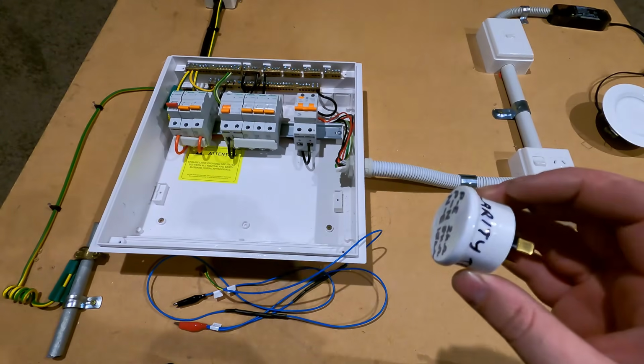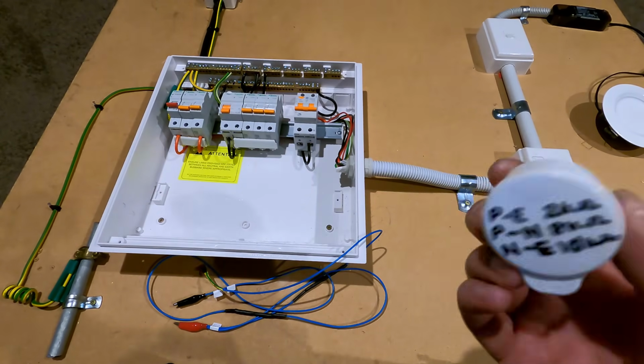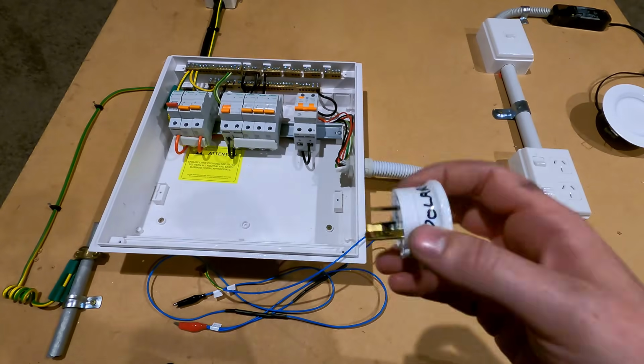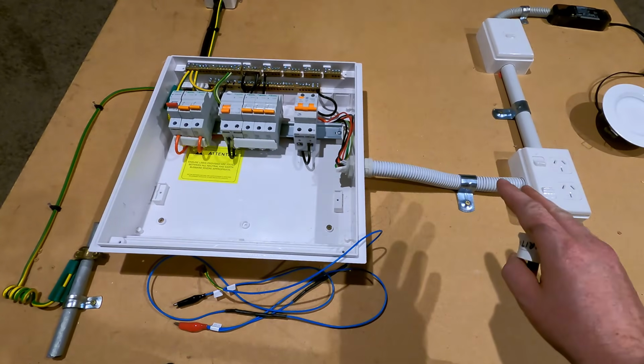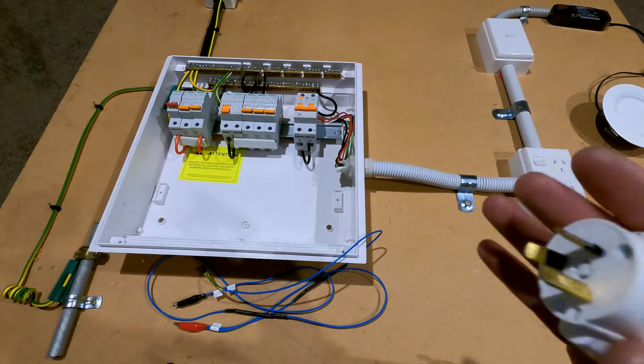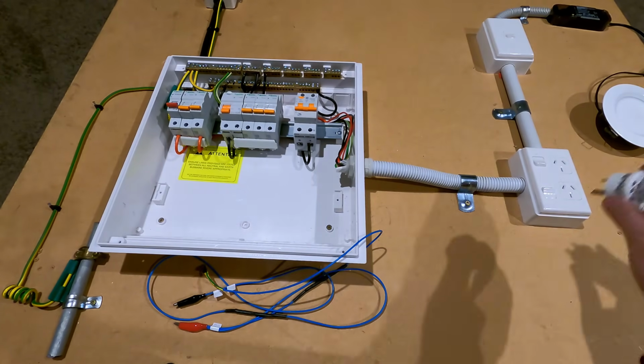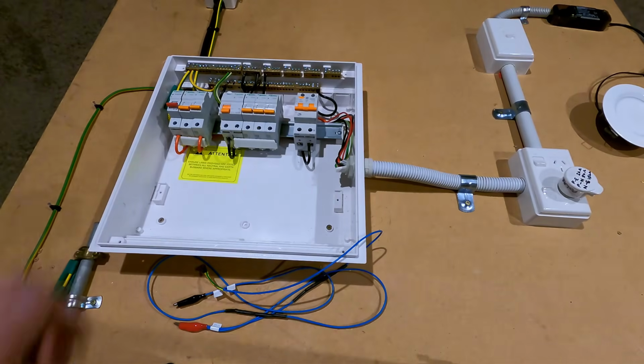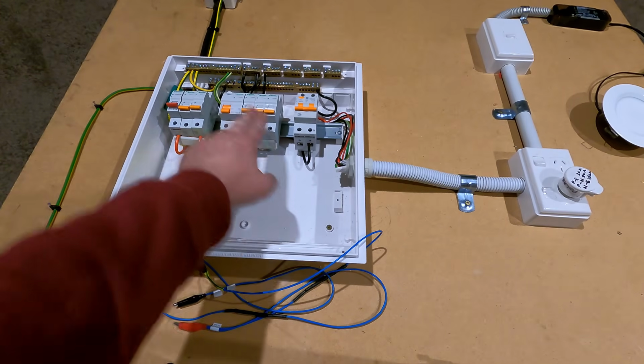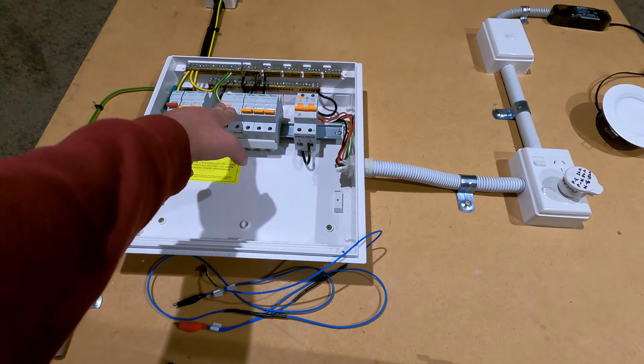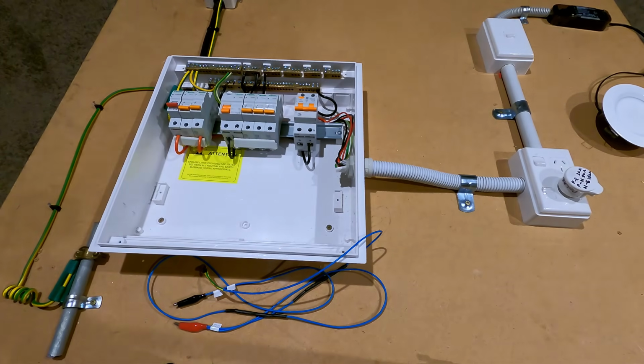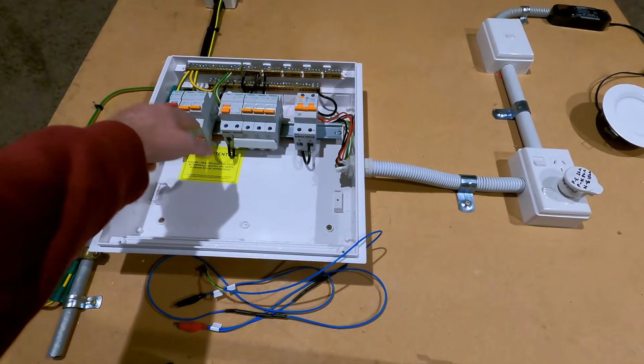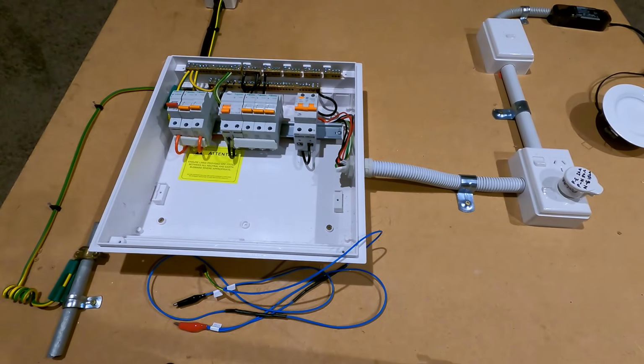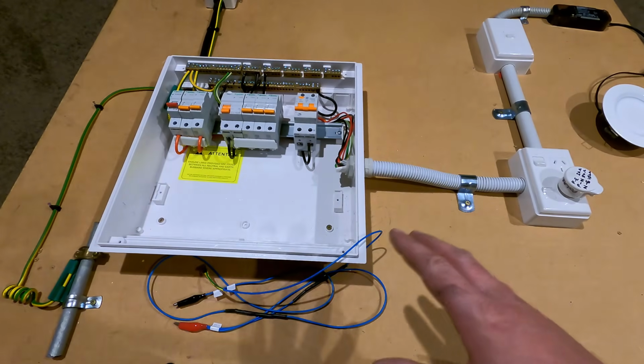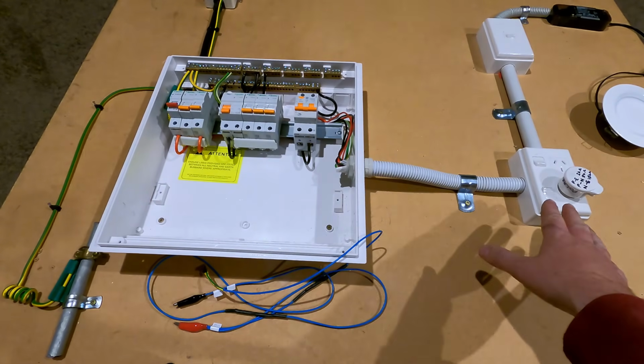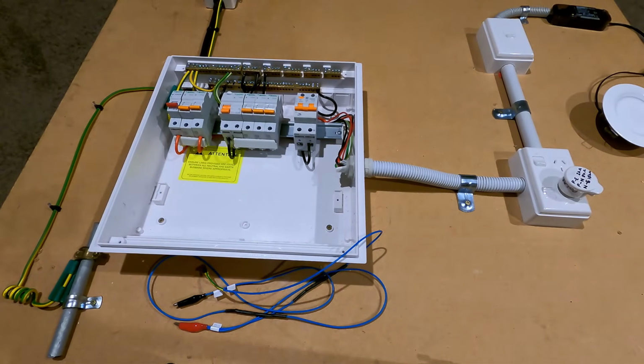So the first one here, I've got known resistances between the 3 pins, and here they are on the camera. So this one here is for doing the socket circuits in a house, and it's really easy because you can just get someone you're working with or an apprentice go around, throw it in each circuit. As long as you have the RCDs in the off position, all of your socket circuits run off the RCDs, so you can leave the MEN link in for that. It's only the fixed load appliances you'll have to take that link out to test. I don't have any on this board today, but I'll run through obviously one socket circuit and one lighting circuit and show you how it's done.